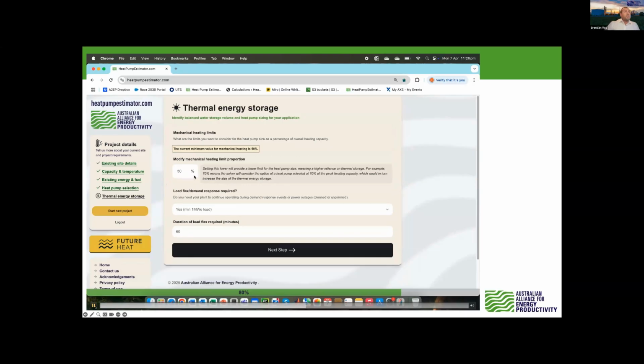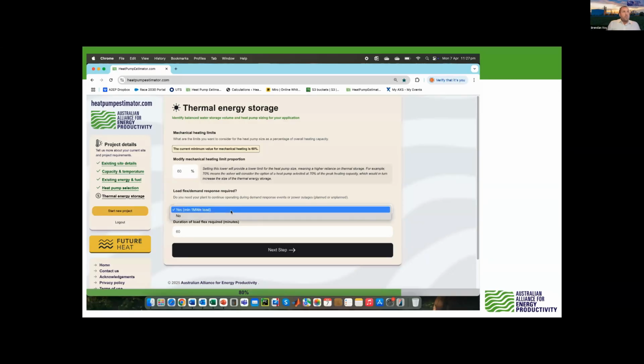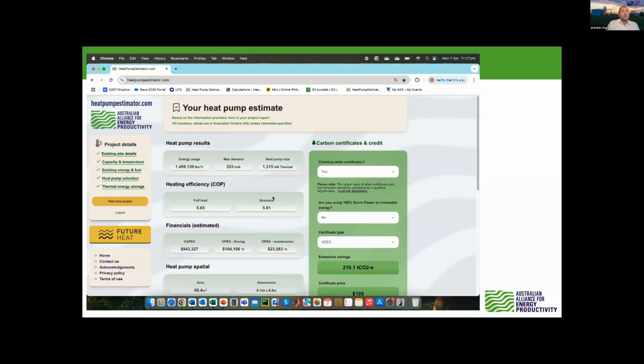Now it's going to ask me here, what do I want in terms of heating for my thermal storage? And this is kind of brand new. The idea here is when you enter in your average up front and you enter in your peak, it will do a division and it will say, okay, you're running at 60% average. Now, if you wound that down to 50, all that's going to happen is the optimization solver in the back is going to let the system rely a little bit more on water and thermal storage. So you'll possibly increase the size of thermal storage and decrease the heat pump. If you do wind it up and you say, no, I'm actually happy with 70, it'll do the reverse. So it'll make the heat pump bigger and the thermal storage smaller, if that's the case. So that's the number you're entering in here. And then finally, do you want to consider load flex or demand response? If you want maybe a 3-hour outage, you would type that in here, basically, and it would add that water storage.